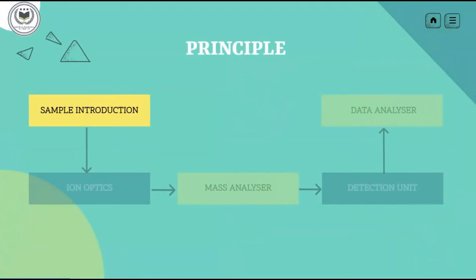The first principle is Sample Introduction. Samples most commonly are introduced as liquids. The considerations made in selecting a liquid introduction system include dissolved solids content, suspended solids presence, presence of hydrofluoric acid or caustic, detection limit requirements, precision requirements, sample load requirements, sample size limitations, and operating budget. The analyst is left with the task of choosing the best introduction components.